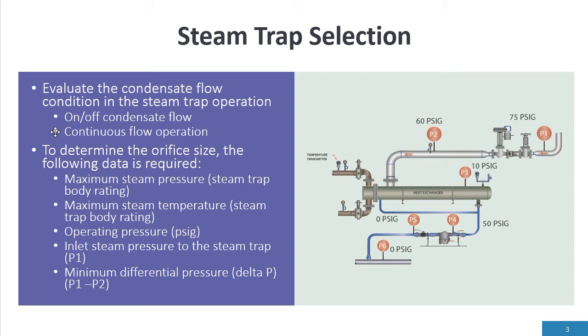The other thing is to determine the orifice inside the steam trap. We need to know the maximum steam pressure or body rating of that steam trap. At P1 we need to know what is the maximum pressure that can be applied to the system. So if the safety valve is set for 150 psi, the orifice inside the steam trap has to be rated for 150 psi.